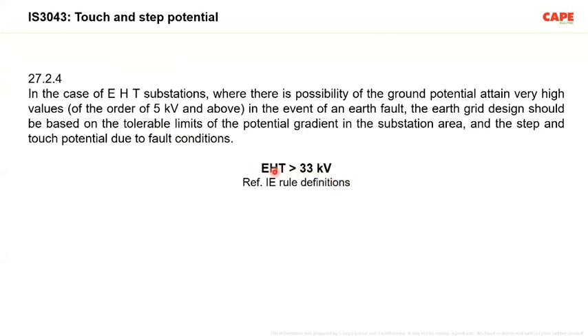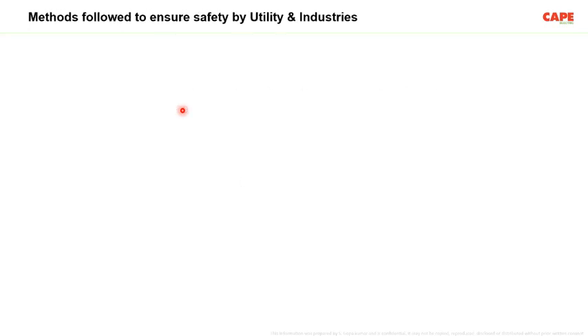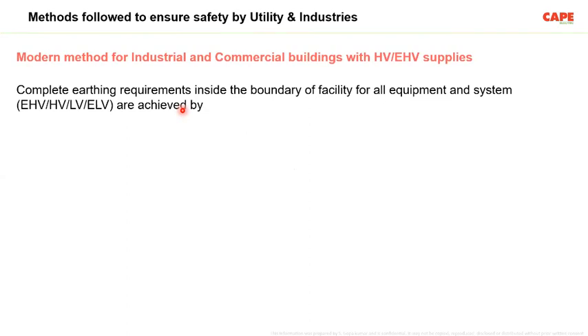However, the definition of EHT itself is nowadays a little bit in conflict. This clause in IS 3043 has existed for more than 25 years. So I took the definition from the IE Rules 1956, because this clause originally dates from before 2010. According to the definition at that point in time, more than 33 kV is an EHT supply. So touch and step potential reduction measures, with respect to the IEEE 80 standard, are necessary for EHT substations. This is the simple definition.